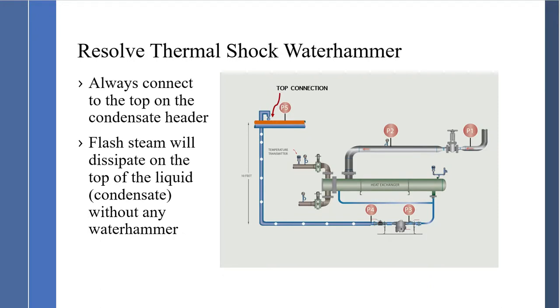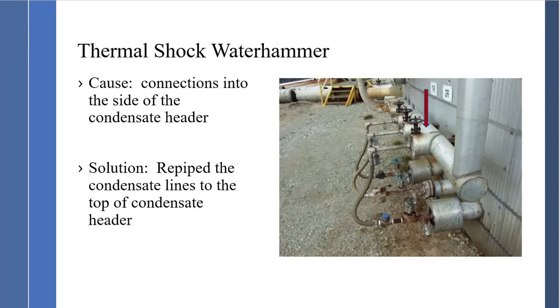To resolve thermal shock or water hammer, always connect to the top of the condensate header. Even if the condensate line is totally filled with condensate, the flash will dissipate on top of the condensate without any noise effect. In condensate systems, the connection always has to be to the top, never the side or the bottom. This resolves thermal shock water hammer.